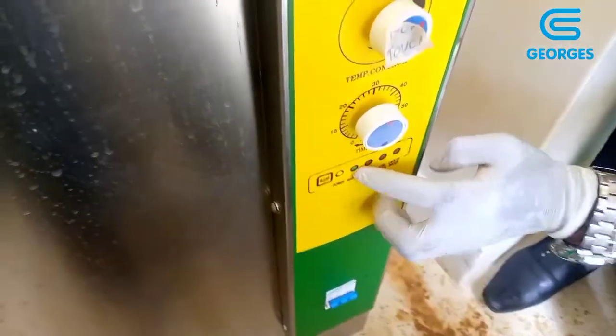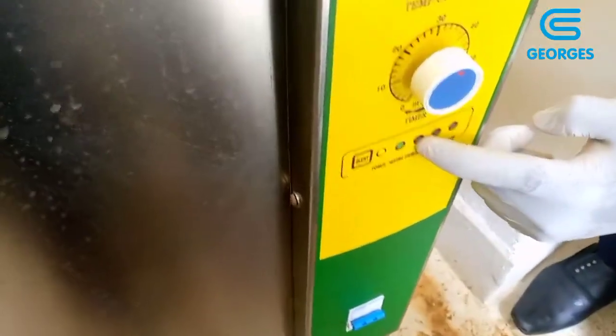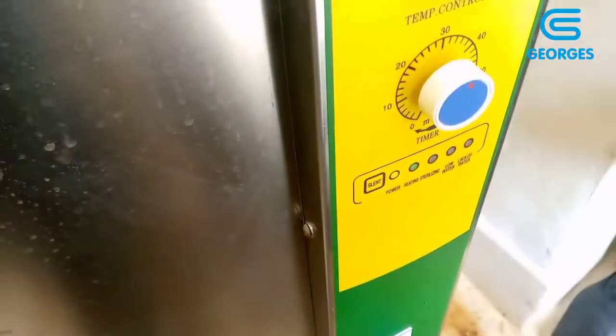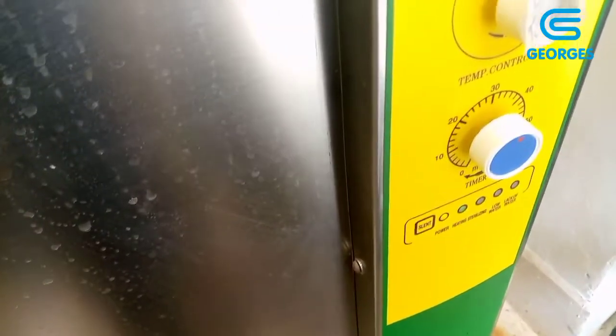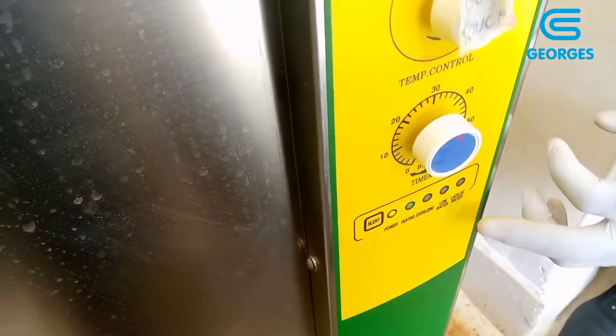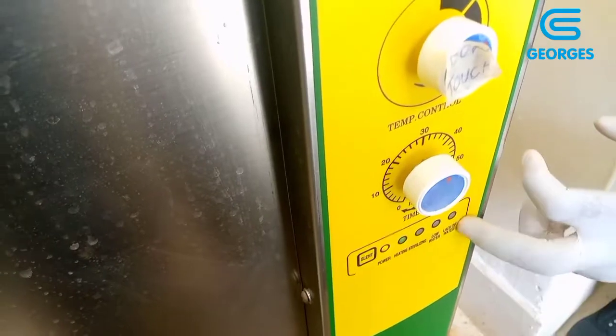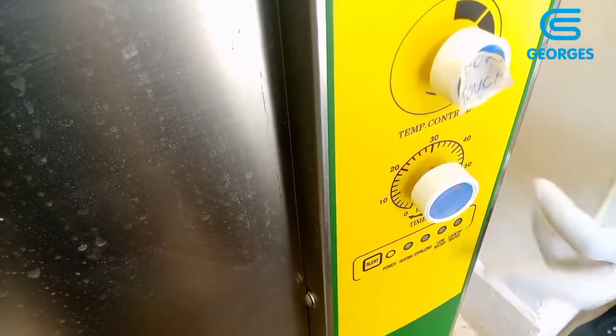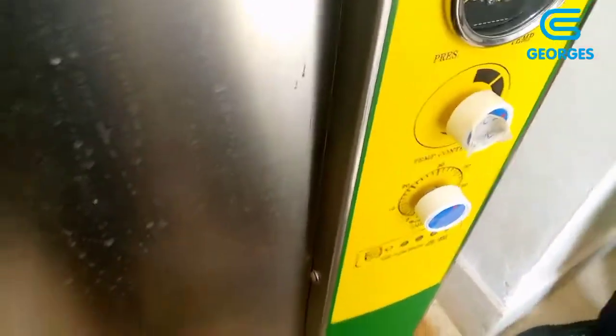You can see the light for heating is on, and the light for sterilizing will come on once it achieves 121 degrees. When the water is low, the machine can also tell you that the water is low. Then when there is no water completely, the machine will tell you that there is no water completely. We'll pick it up from there.